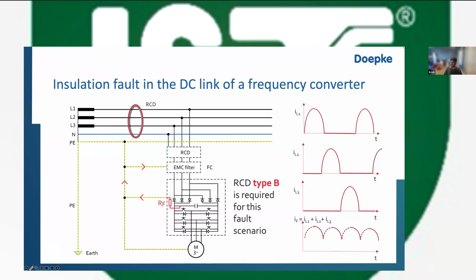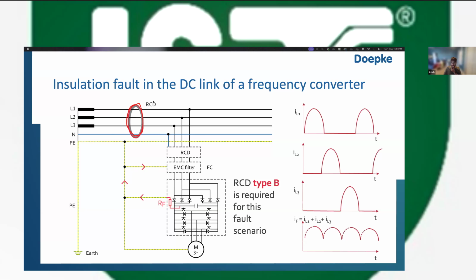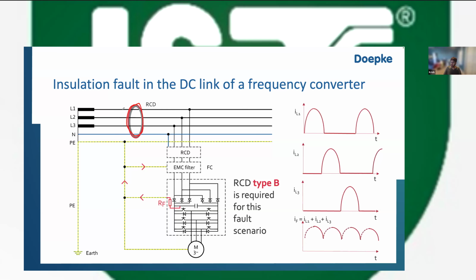So basically in every RCD you have a toroid like this red circle over here, and it is monitoring how much current is going through the line conductors and how much current is coming back through the neutral or any of the other lines. Say we talk about a single phase load: through L1 we have 1 ampere, and through neutral we also have 1 ampere. We know that when alternating current, which is a changing magnetic field, flows through a coil, a current is induced in that coil. But here the current in and the current out are the same, so there is no net current.